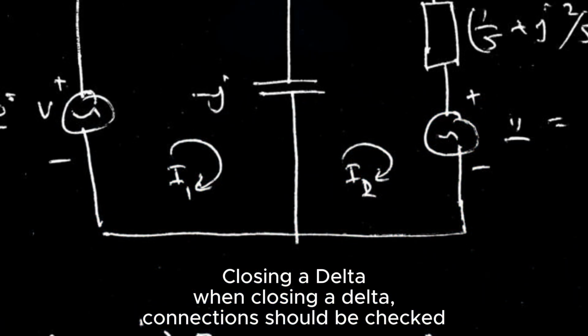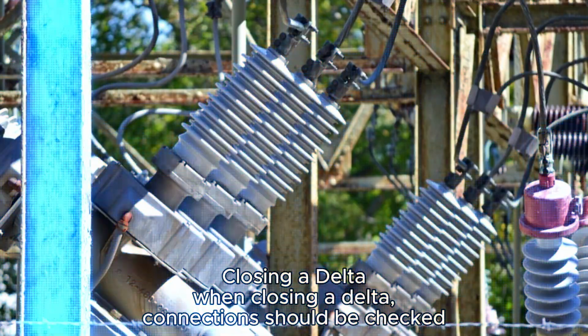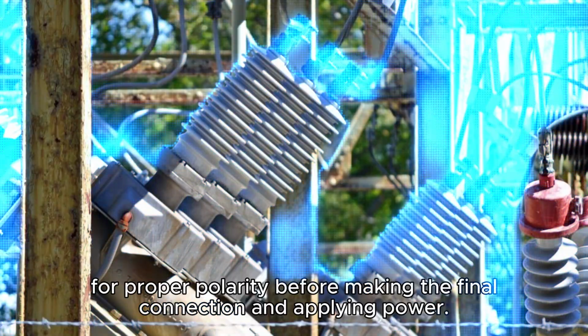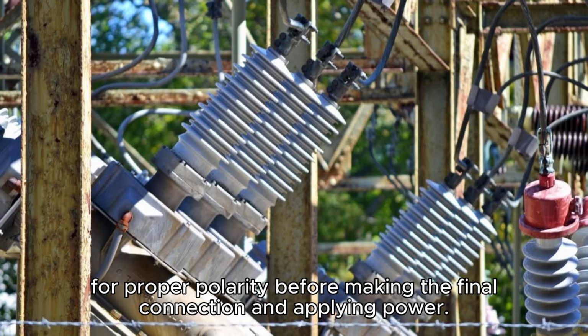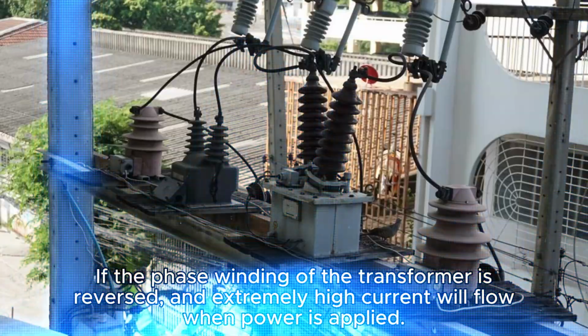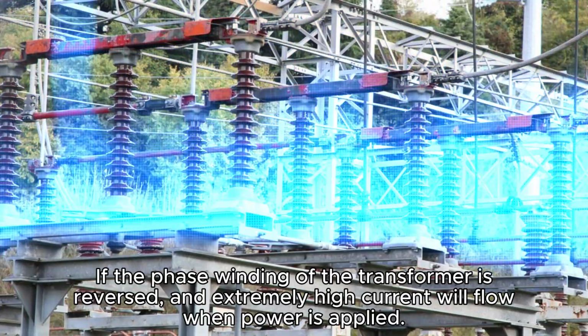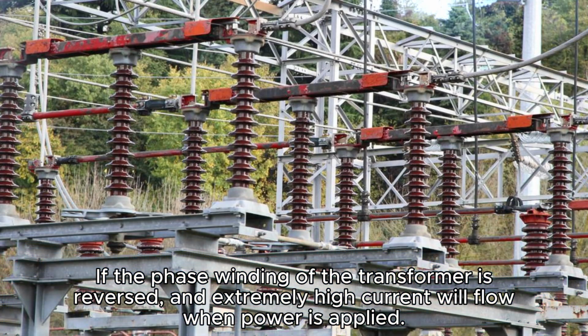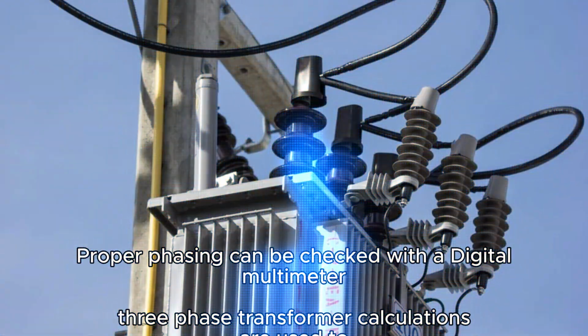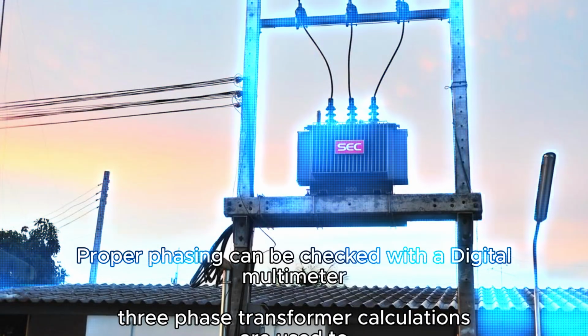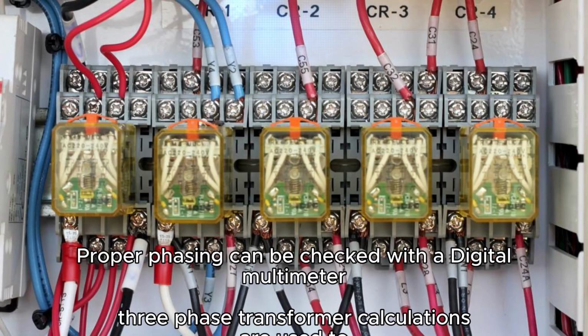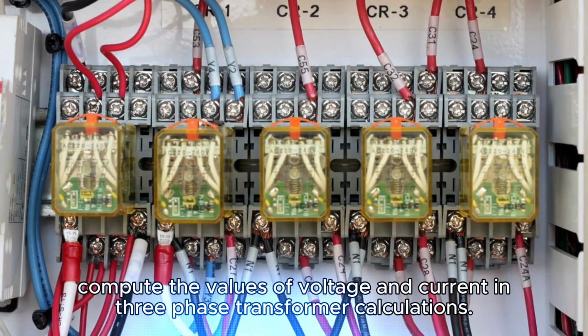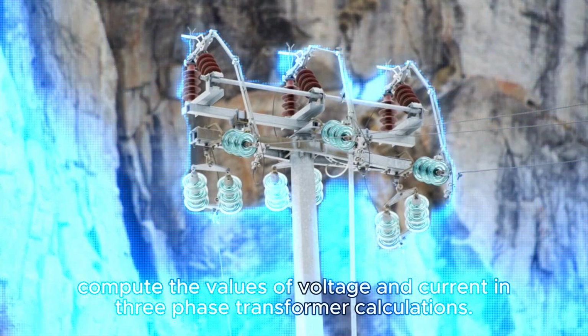Closing a delta: when closing a delta, connections should be checked for proper polarity before making the final connection and applying power. If the phase winding of the transformer is reversed, an extremely high current will flow when power is applied. Proper phasing can be checked with a digital multimeter. Three-phase transformer calculations are used to compute the values of voltage and current in three-phase transformers.